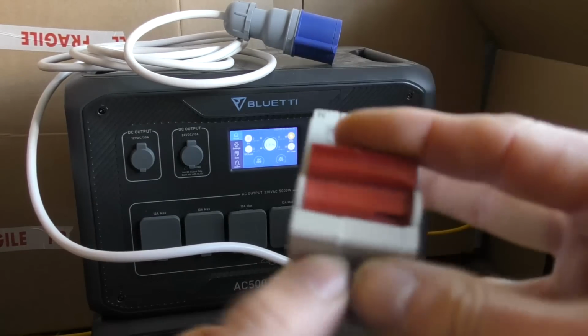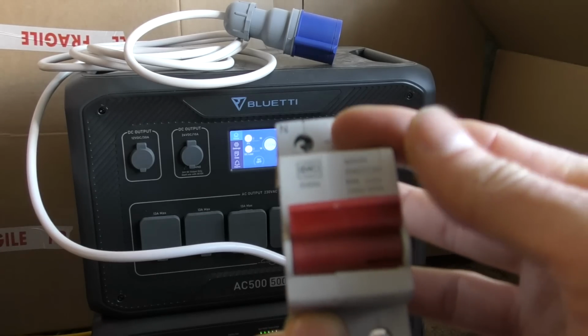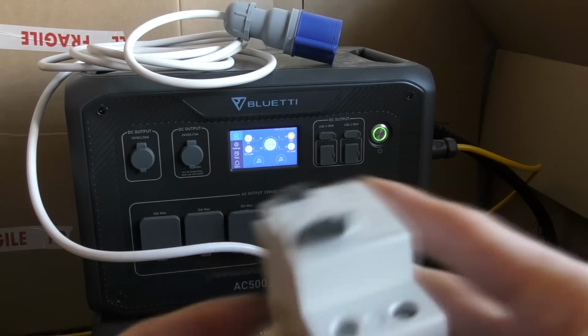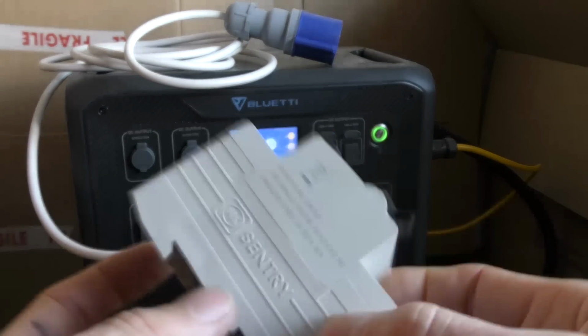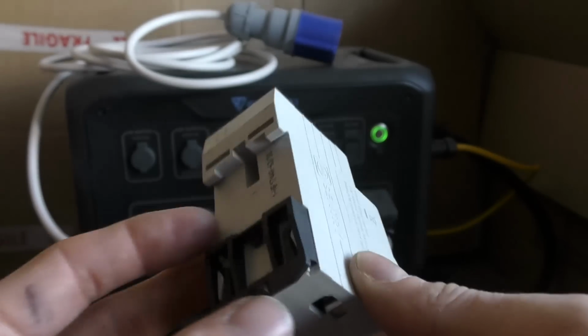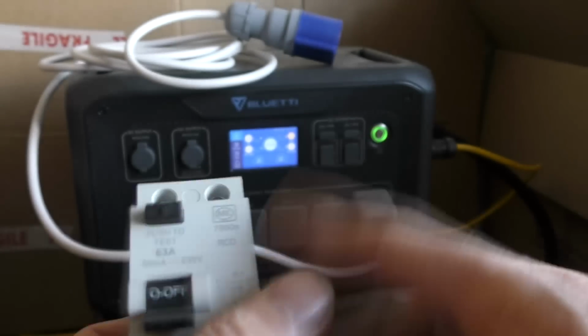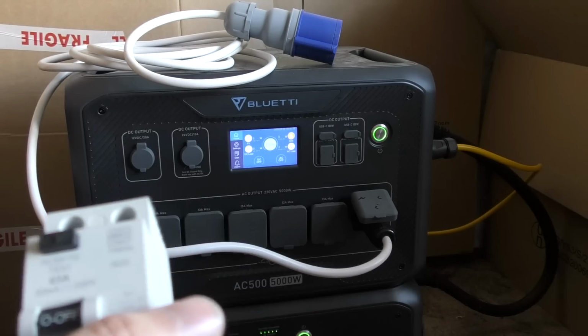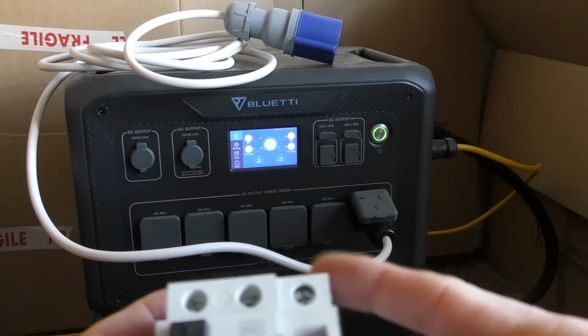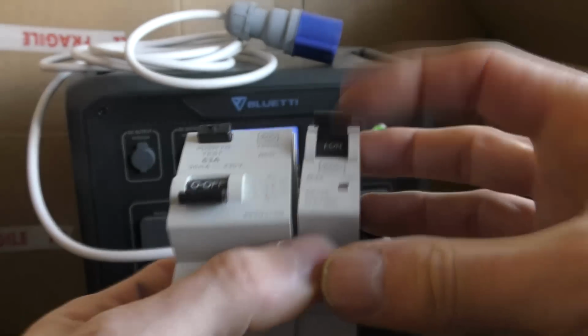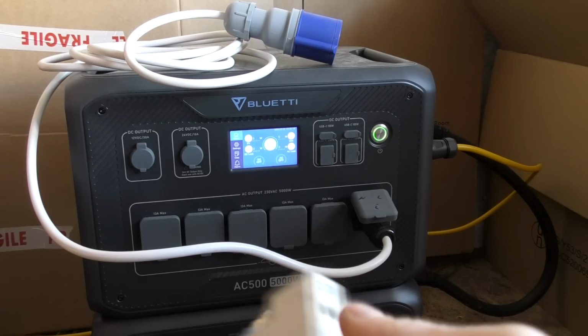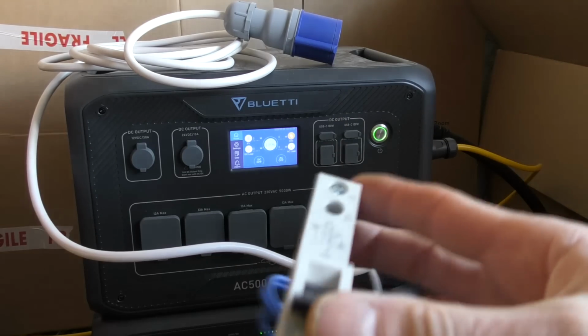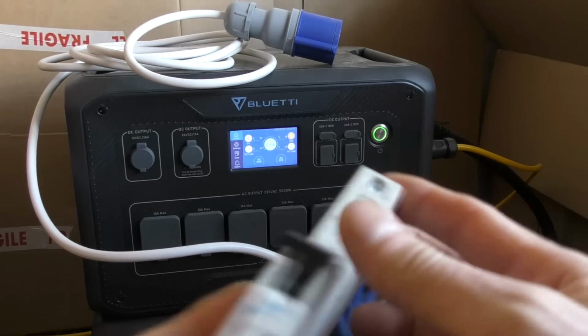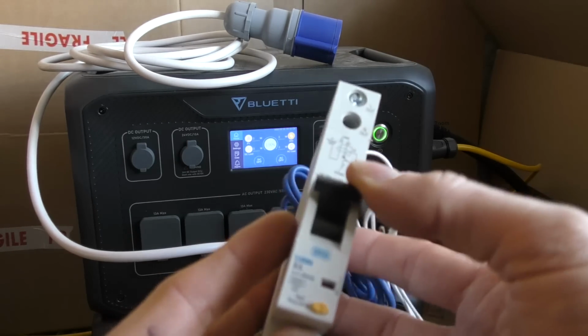Typical UK distribution boards have a 100 amp isolator on the incoming supply, and a very common situation is that this is then split into two and feeds two RCDs, residual current breakers, or GFCIs as they call them in the US, and then half your circuits connect to each one via standard overcurrent circuit breakers like this. The other, more modern approach is where you just have the incoming main switch and an RCBO. This is effectively a combined circuit breaker and residual current device.